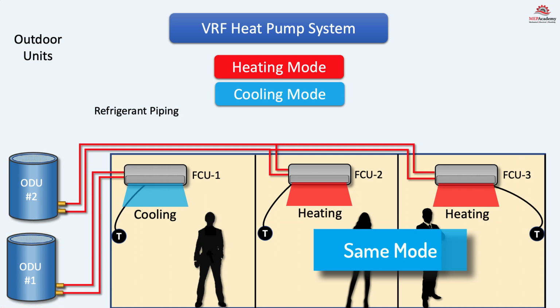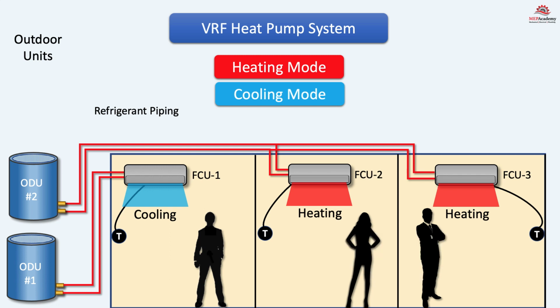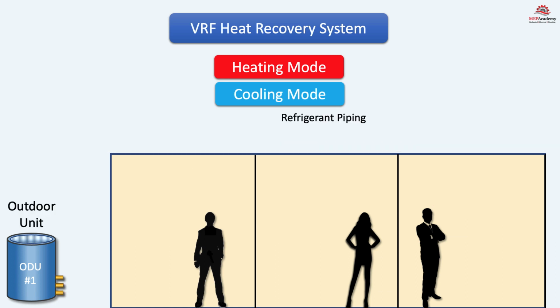The benefit of using a VRF heat pump system over the traditional split system heat pump is that you have an inverter compressor and multiple indoor fan coils all working together to achieve a lower energy consumption.